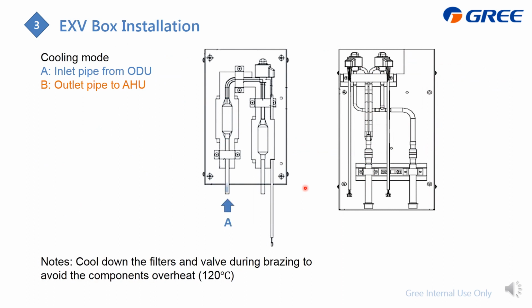This is how the refrigerant flow inside the EXV box. In cooling mode, here is the refrigerant in, and it will get expanded at this EXV and then flow out. As for the 2EXV model, here the refrigerant in and divided into two flow and also get expanded at the EXVs, and then they combine together and flow out. And during the installation, please pay attention that you should avoid the overheating, as the EXV is sensitive.